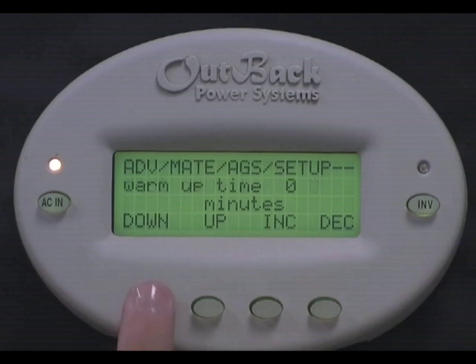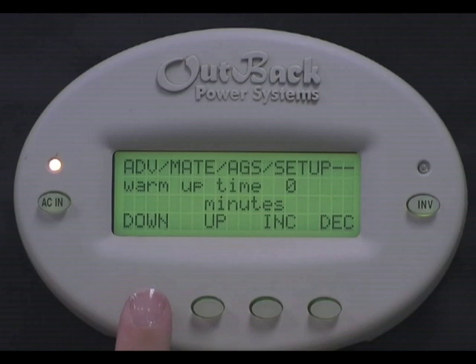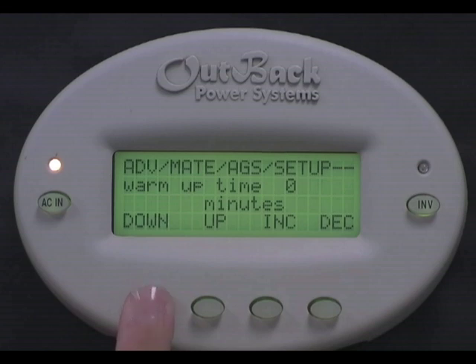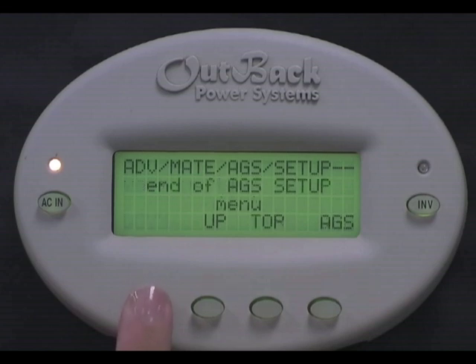Press down. Warm up time can be programmed to be anywhere from 0 to 30 minutes. Check with your generator manufacturer to see what the optimal warm up time for your particular generator would be. This number must be less than the AGS fault time, otherwise your system will fault. Press down.